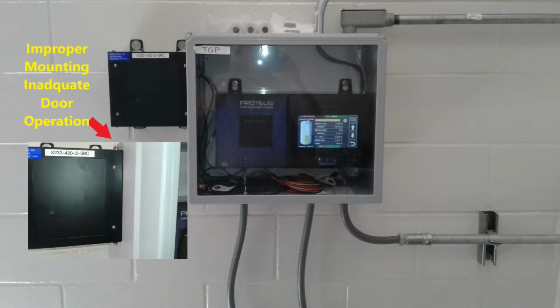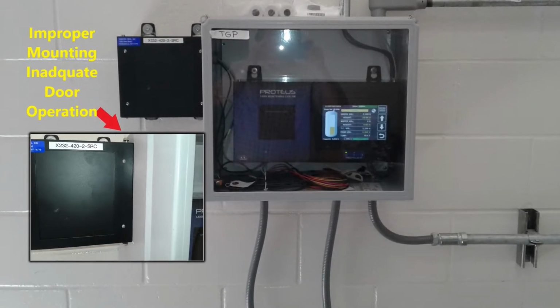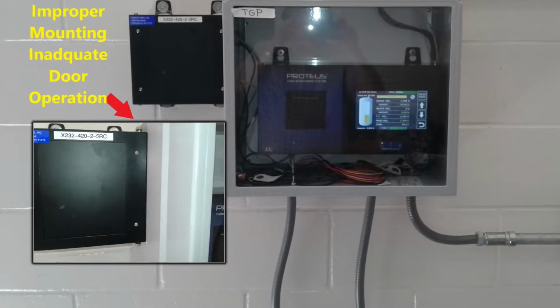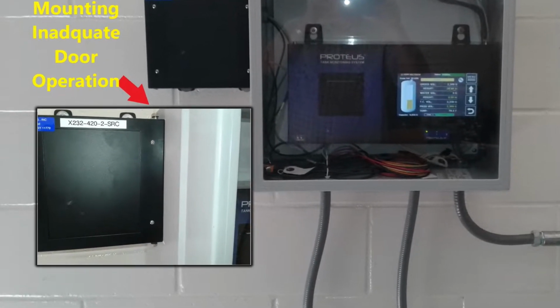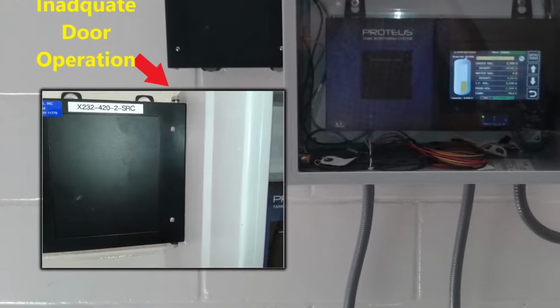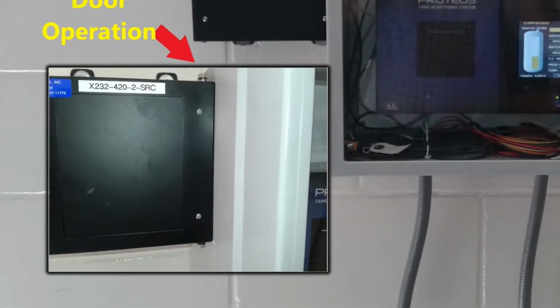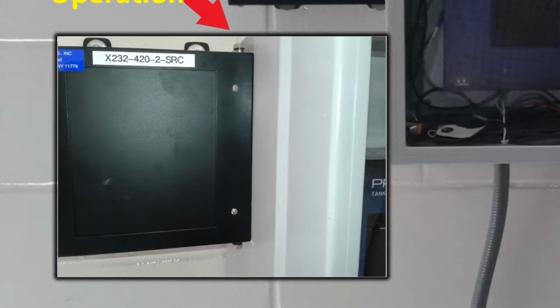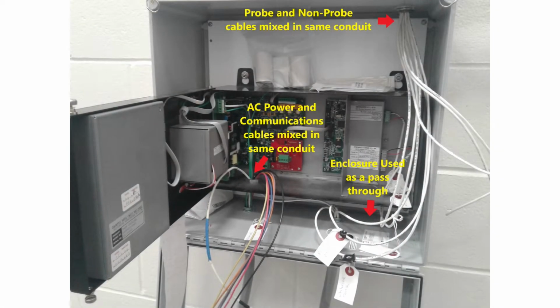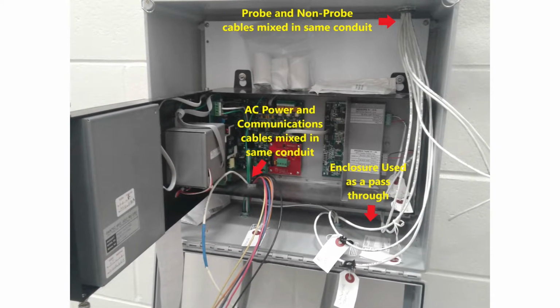Let's take a quick look at some installation issues seen in the field. Here we see that the external 4 to 20 mA converter box, the X232-420, was mounted butted up to the controller's NEMA 4X enclosure. This did not allow for the door to open properly. This installer was trying to save on the number of conduits used.